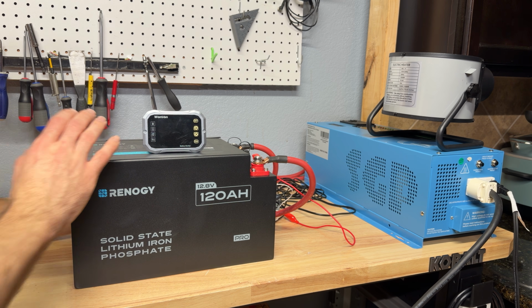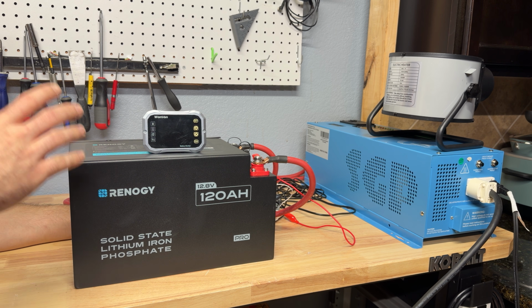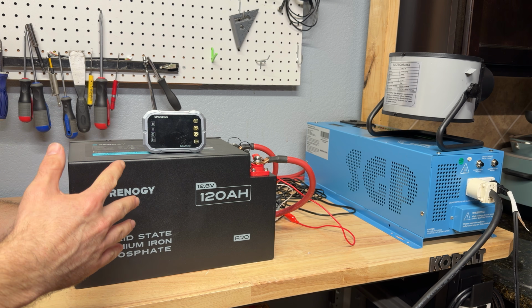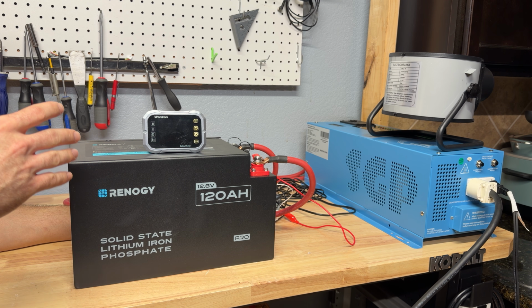I spoke too soon. All right, so they rated it at 150 amps. I got it to about 165 before it actually tripped, so that's pretty close to the rating, and I'm happy to say that the high current discharge protection does work.